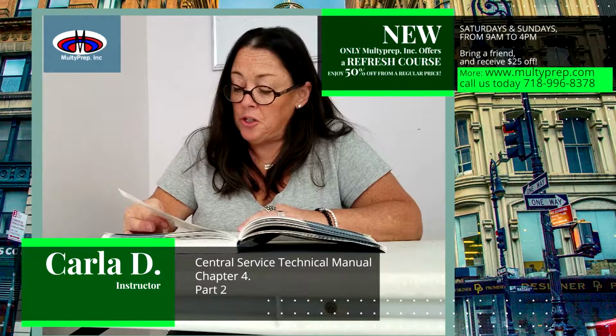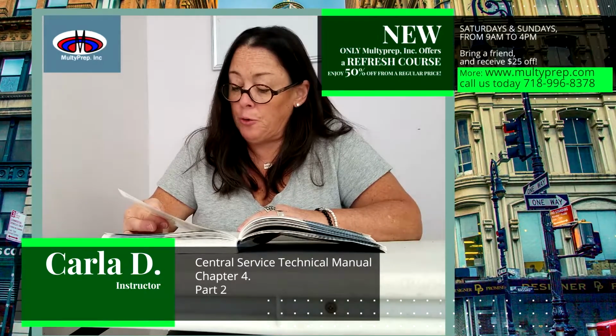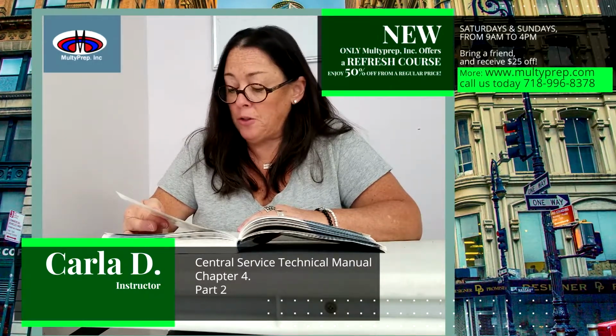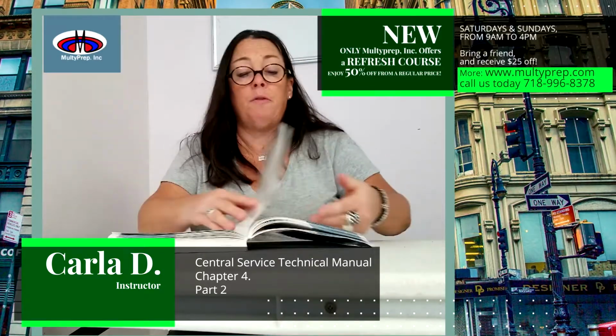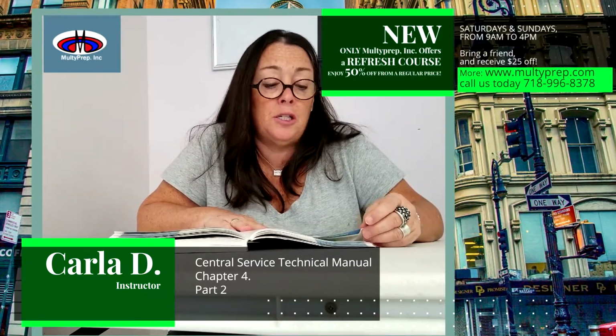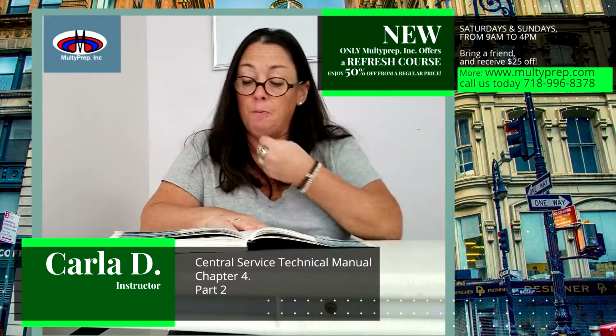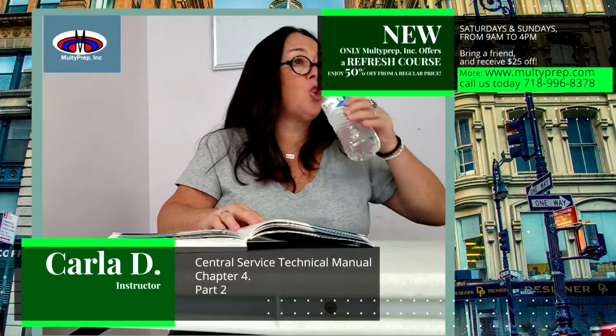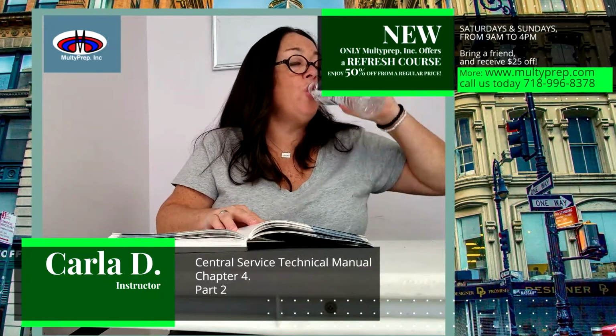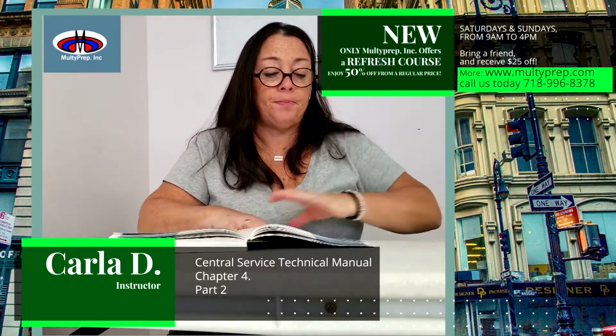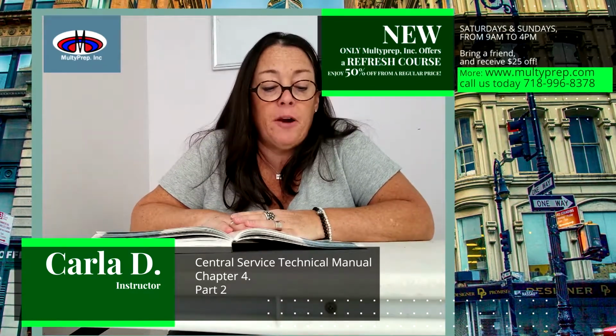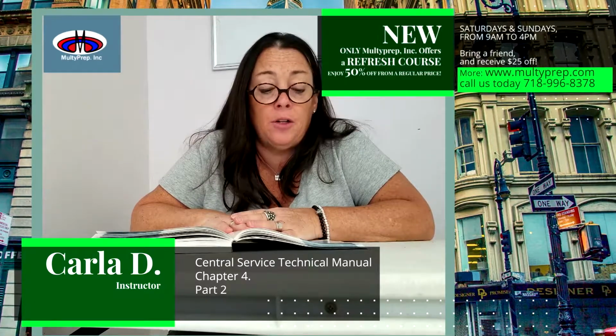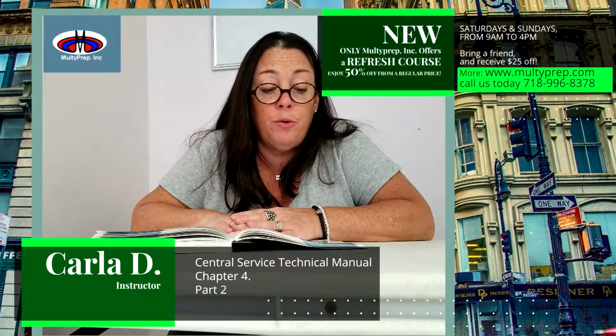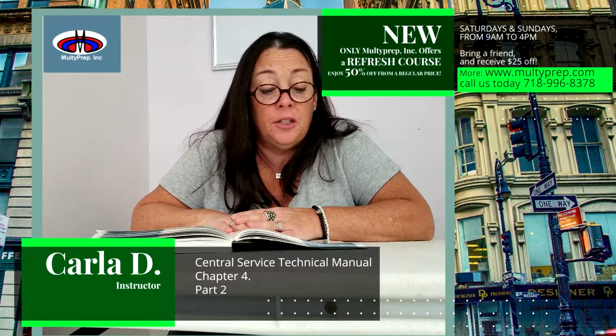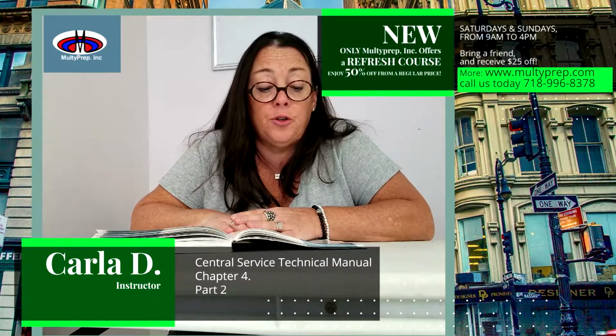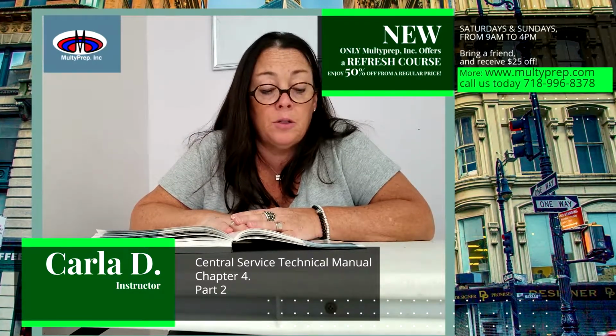When a suspected CJD patient undergoes a procedure, all healthcare professionals involved with that patient must be notified, and the facility's CJD policies and procedures must be followed. Cleaning and sterilization of items contaminated with prions is a challenge, as prions are difficult to remove or deactivate, and standard cleaning and sterilization procedures are ineffective against prions.